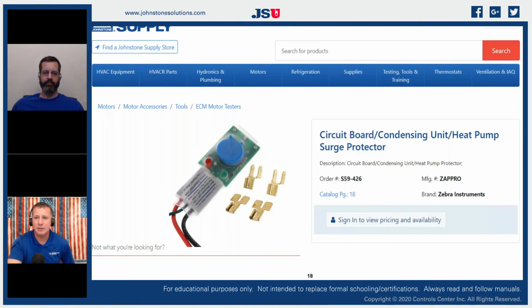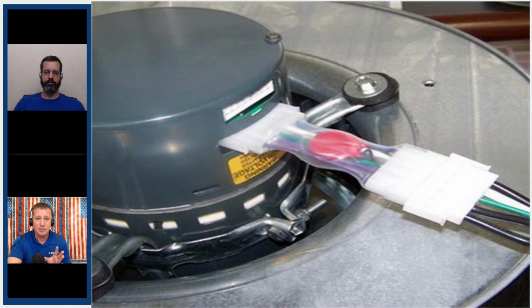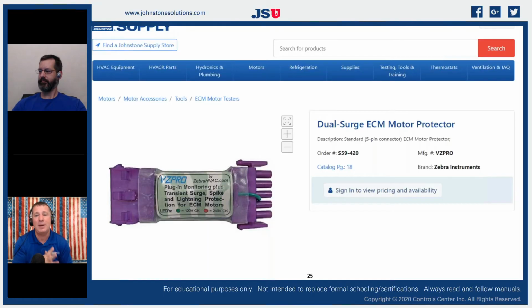So they've got the little Zap Pro, that's one that can be added for outdoor units, AC and heat pumps, just to help protect the control board itself. But then we've also got, along those lines, a surge protector that's designed to protect ECM motors specifically. So the 5-pin power connector that is coming into that module on the back of your ECM blower motor, this is designed as a plug-and-play surge protector for that. And I highly encourage these on ECM motors.